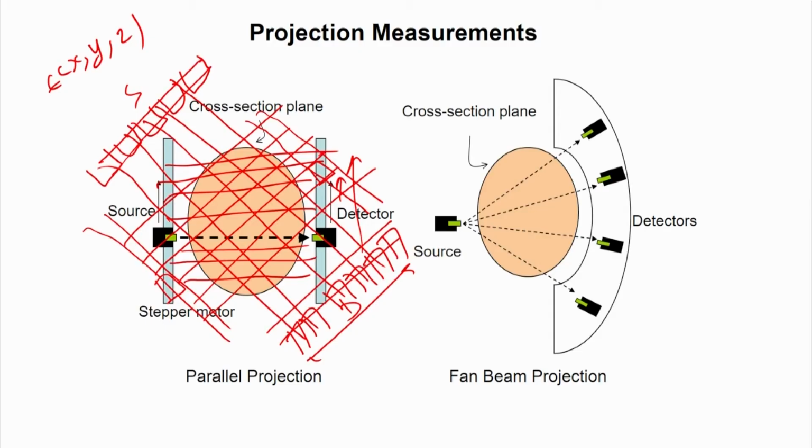So that is the drawback, and to overcome that, the fan beam projection is used, in which we take a source and design the collimator in such a way that it generates a fan beam. Now, along the length of the beam, one detector is placed. As we can measure the angle at which it will be emitting these gamma rays, we can find where to put the detectors. So, each range has one detector, and you can find the pixel information, the line average information, from each detector.